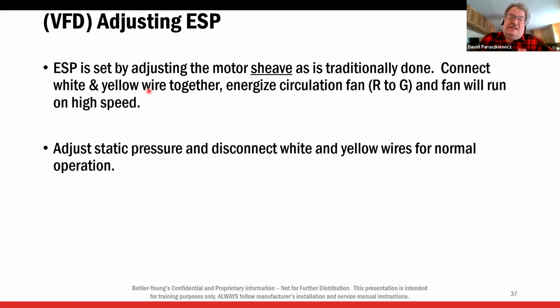All right. Static. Now, there's a reason these don't come with a keypad, you're going to see the keypad in a minute. The reason is because Bryant doesn't want you messing with the setup in the drive. And on variable speed equipment, they'll actually use the drive and adjust the blower to static. That's not what we're going to do. We're adjusting static pressure like we always have, or like you always hopefully have, by adjusting the pulley, all right? Not by screwing with the drive. So there's a red and yellow, or a yellow and white wire in there. You're going to jump them together. You're going to put energized G, check your static, and then you can adjust your pulley or sheave like you always have. That's how you adjust static on these, not through the drive.